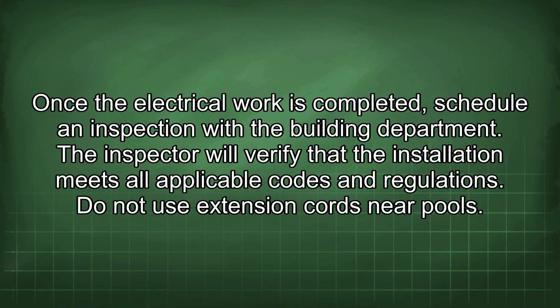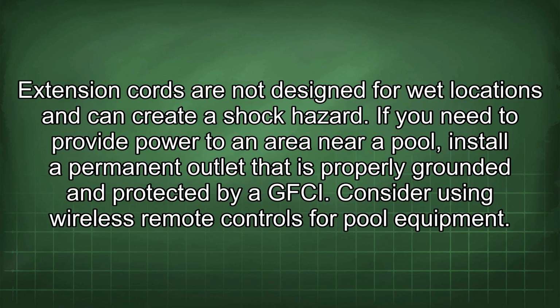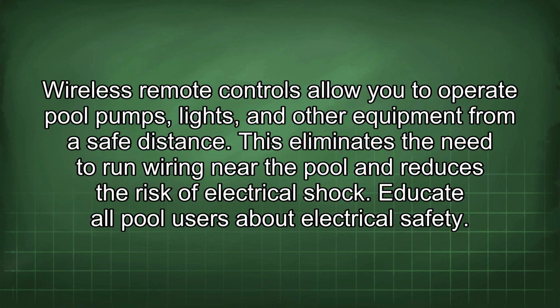Do not use extension cords near pools. Extension cords are not designed for wet locations and can create a shock hazard. If you need to provide power to an area near a pool, install a permanent outlet that is properly grounded and protected by a GFCI. Consider using wireless remote controls for pool equipment. Wireless remote controls allow you to operate pool pumps, lights, and other equipment from a safe distance. This eliminates the need to run wiring near the pool and reduces the risk of electrical shock.